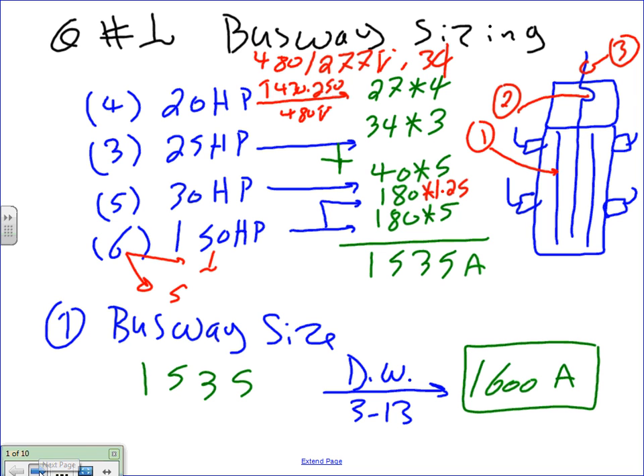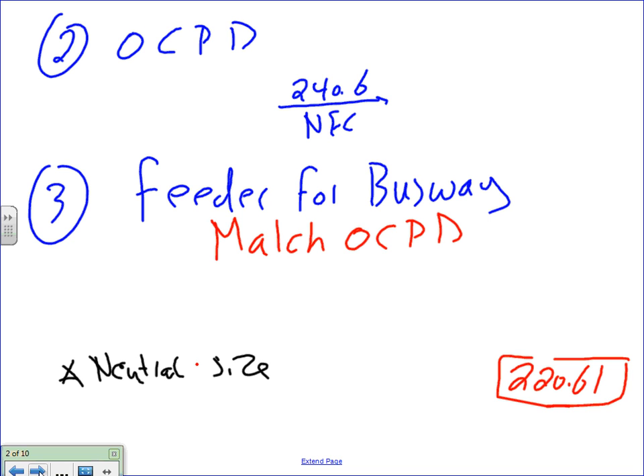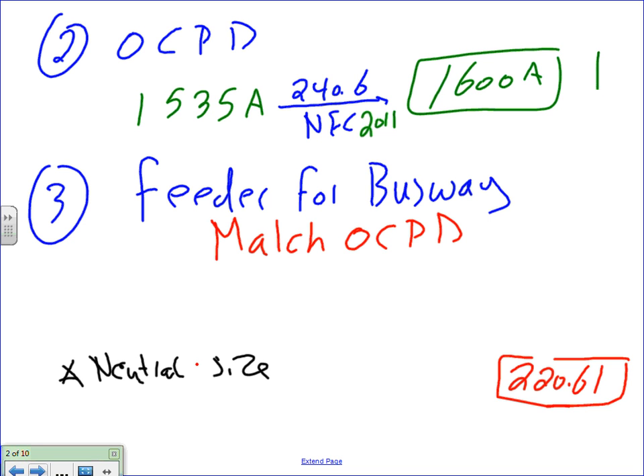Done? Thank you. Okay. The next, guys, piece of cake. The next that we need to do is we need to go, I want to write with green. The new stuff is going to be colored green. The next is we need to go size the overcurrent protection device. What I would do, I use the same amp for sizing the overcurrent protection device. 1535 amps. Take it this time to 240.6, and if you guys go there, the next standard will be 1600. So we hit the jackpot. And if it's not a standard, where do we go? We go up to the next standard, 1600. So we have a 1600 amp circuit breaker to feed this baby.